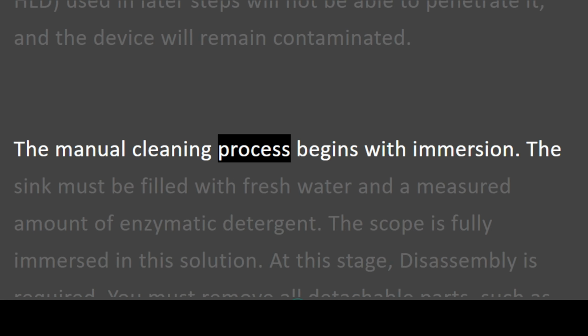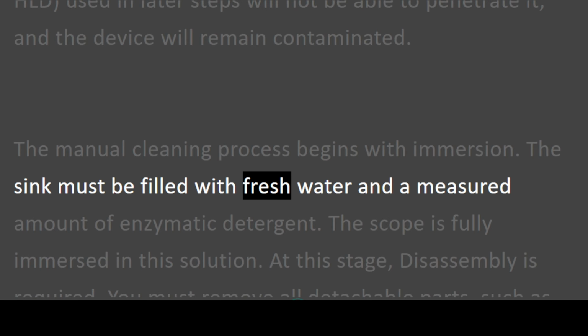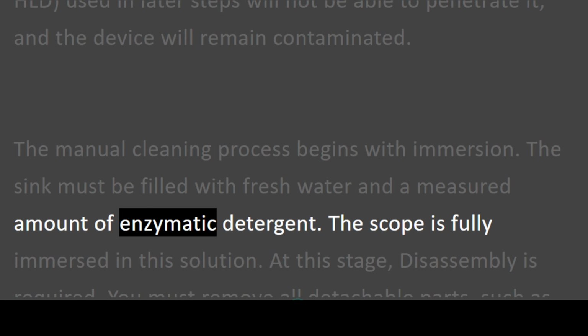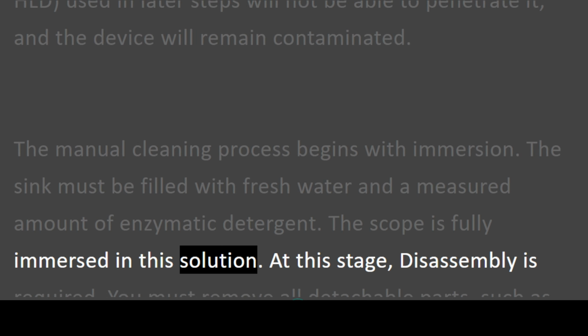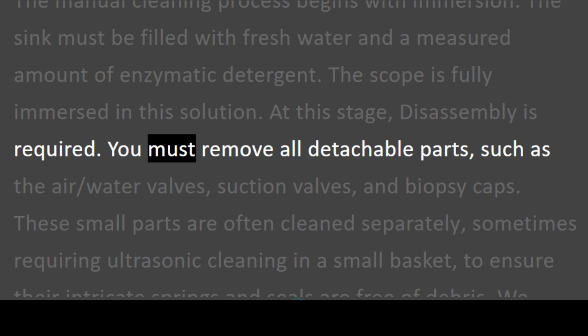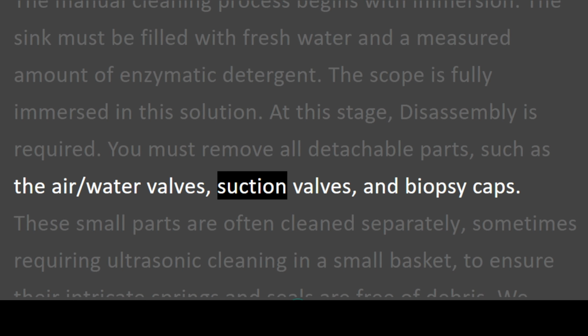The manual cleaning process begins with immersion. The sink must be filled with fresh water and a measured amount of enzymatic detergent. The scope is fully immersed in this solution. At this stage, disassembly is required. You must remove all detachable parts, such as the air/water valves, suction valves, and biopsy caps.